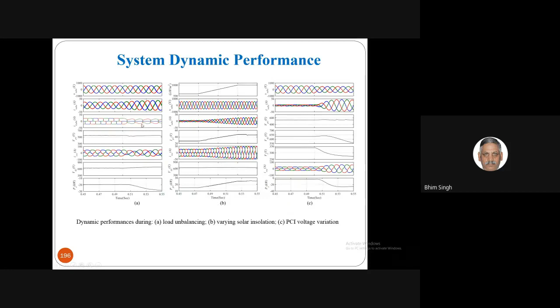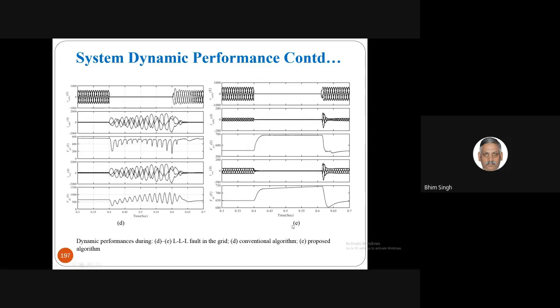condition, because the new standard says even if there is a fault, you have to keep the inverter connected. There are two reasons: you can support the grid from the inverter, either by reactive power or active power, which you can feed there, taking care of the fault recovery. And when suddenly the fault is removed, you should come to steady state very quickly if your inverter is on. If the inverter is not on, you have to synchronize again. It takes some time, so you lose some energy also. So under fault condition it will remain connected to the system.